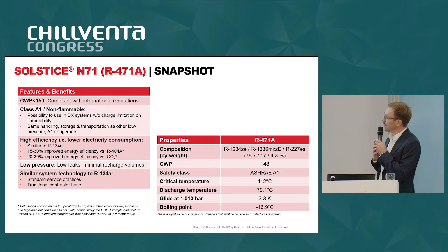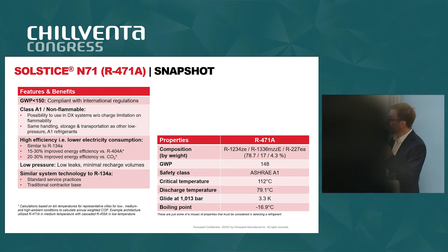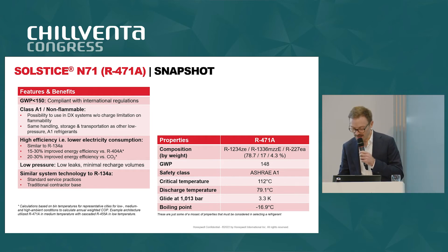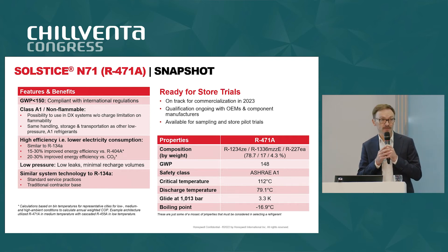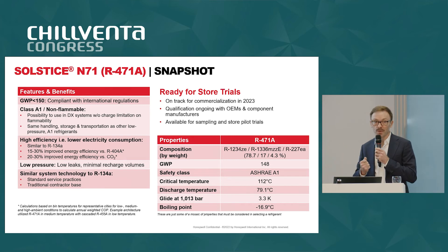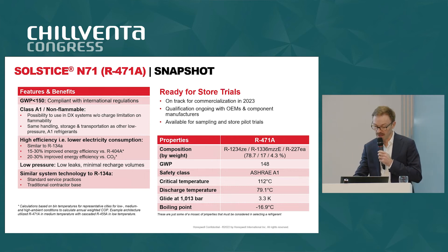In terms of properties, it is a blend made out of mainly 1234ZE, a bit of 1336mzzE, and 227EA. GWP is just below 150. With a boiling point of minus 17°C, this is a refrigerant for medium temperature applications — it does not cover low temperature, so it is not a replacement for 455A but a complement. It plays in larger formats, typically above 40 kilowatts for medium temperature. We are ready for store trials — this product is available for sampling and pilot trials in stores, and we are on track to commercialize.